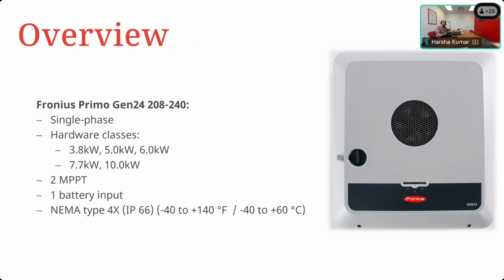In addition to that, the operating temperature range we maintain the same. It's minus 40 C to plus 60 C. If the temperature were to be below minus 40 C, the inverter will basically stop functioning in order to protect itself. On the high side, it can work up to an ambient of plus 60 C. If your ambient is higher than plus 60 C, then the fans will kick in, but typically you tend not to have ambient temperatures of plus 60 C unless you're inside an unventilated enclosed space. In which case, it will start derating, basically throttling how much power it puts out.